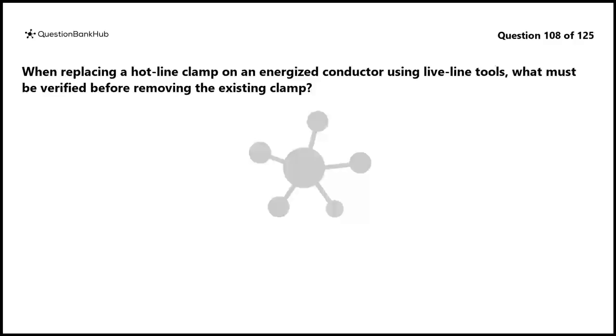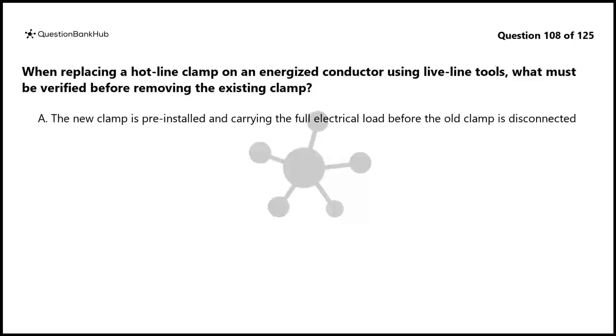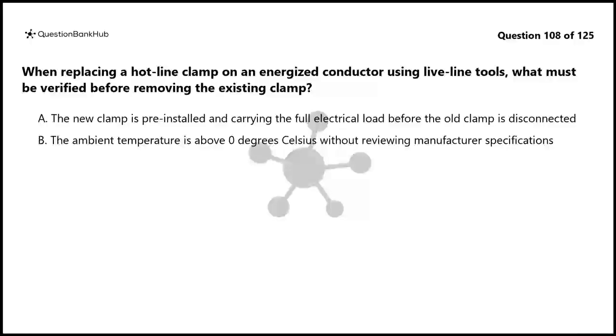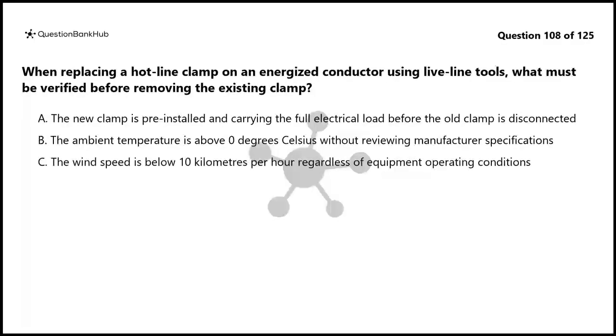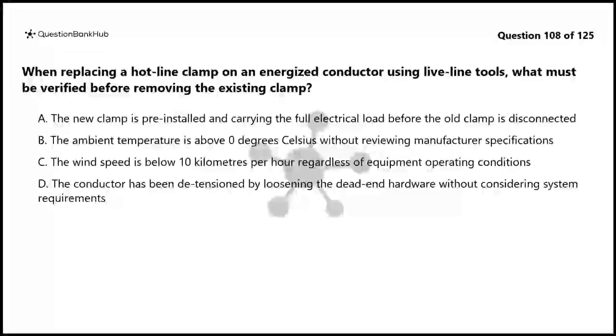Question 108. When replacing a hot line clamp on an energized conductor using live line tools, what must be verified before removing the existing clamp? A. The new clamp is pre-installed and carrying the full electrical load before the old clamp is disconnected. B. The ambient temperature is above 0 degrees Celsius without reviewing manufacturer specifications. C. The wind speed is below 10 km per hour regardless of equipment operating conditions. D. The conductor has been detensioned by loosening the dead-end hardware without considering system requirements.